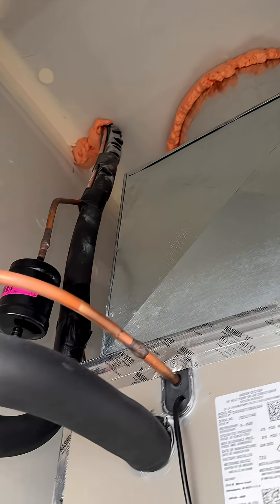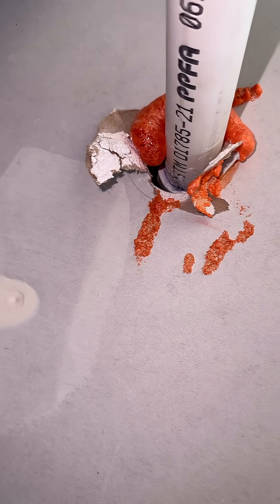In almost every new house furnace room I inspect, they only seal the side you can see. They never seal the back side of these openings. You can see the missing fire foam here, and here, and again here.